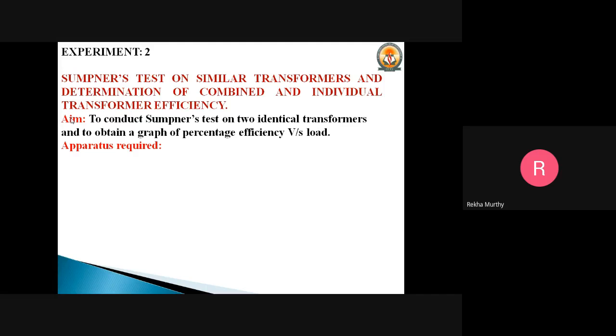So why do we have to conduct the Sumpner's test? Though we know the efficiency and the regulation of a transformer can be determined from the OC and SC tests, as discussed in the previous session, that can be determined accurately, but for the determination of temperature rise, it is required that the transformer be put on full load for a number of hours.